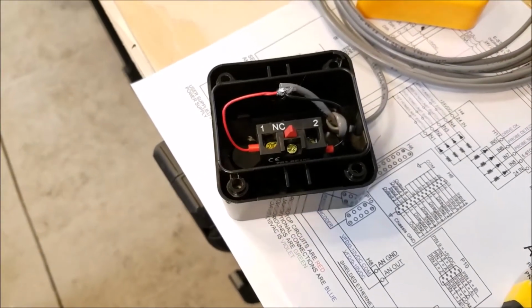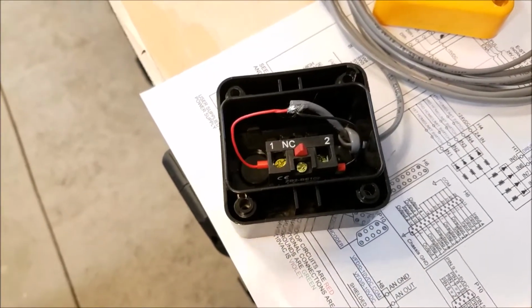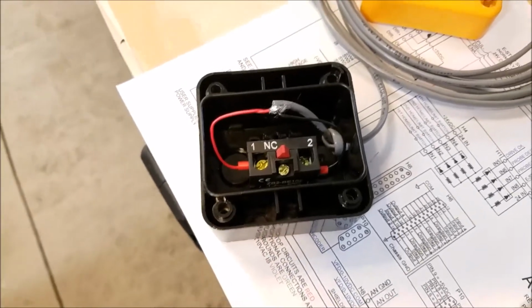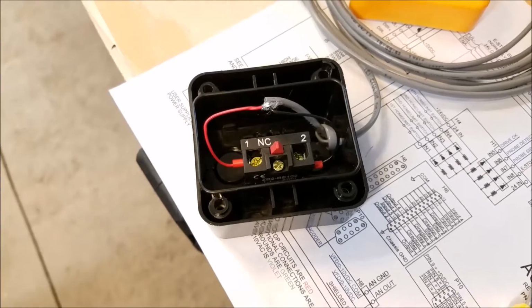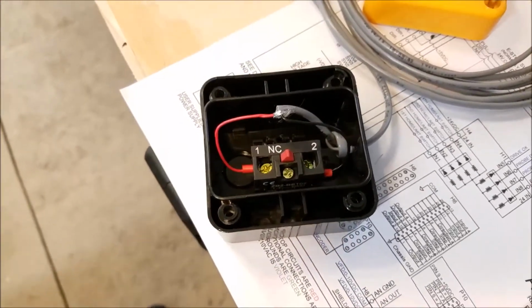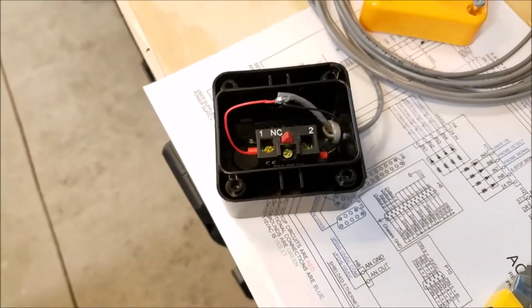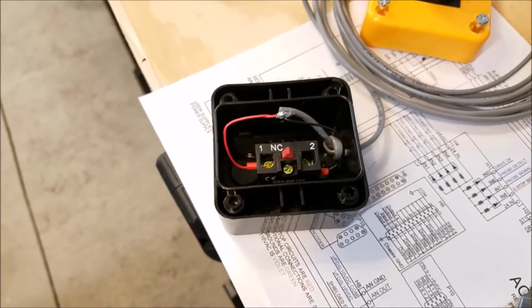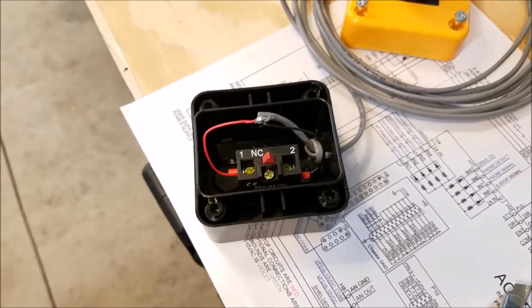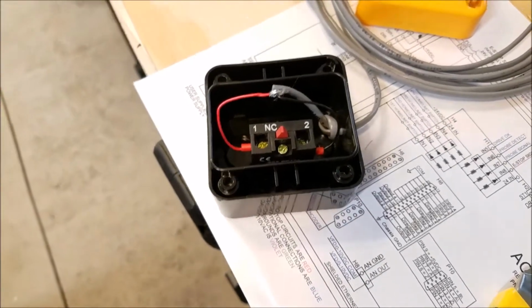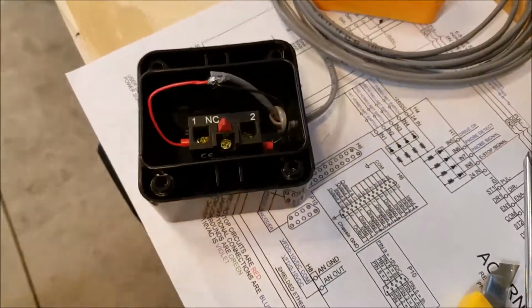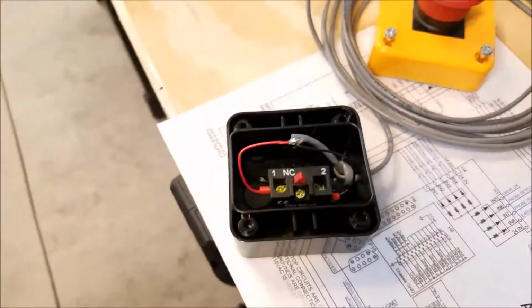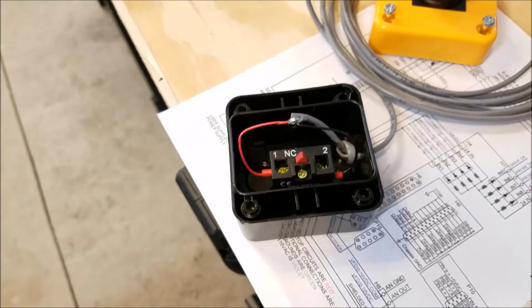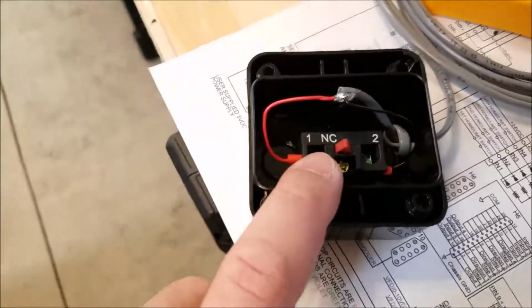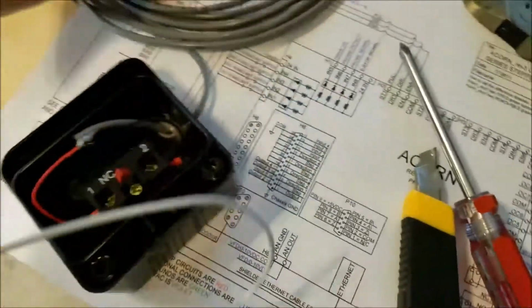When you think about the potential failure mode, imagine the situation where the cable to your e-stop gets cut. Normally closed, if the cable gets cut, that opens the circuit. It triggers the e-stop. It stops the machine. If you wire up your e-stop normally open, now the system thinks when the circuit's open, everything is okay. Well, imagine now you've accidentally cut your e-stop cable. It's still open. The system still sees it open. Now you have an emergency. You need to stop the machine. You can't stop it. There's no way to close it because you've cut your e-stop cable. So that's why e-stops are generally wired up normally closed.